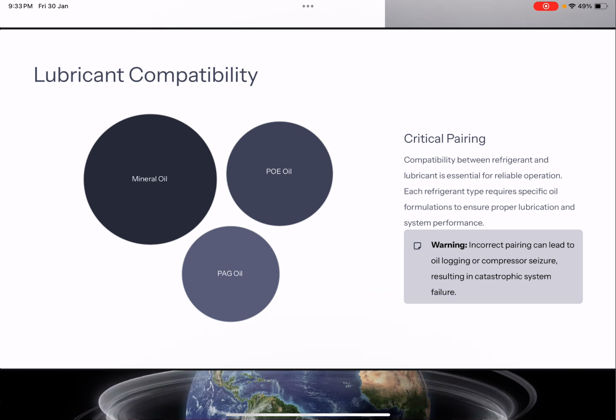As I said earlier, compatibility with the lubricant, essentially compatibility with mineral oil or POE, is important because that is going to affect the life of the components in the long term. If there is an incorrect pairing, meaning a refrigerant going along with an incompatible lubricant, then that might lead to oil logging or compressor seizure, and that would result in catastrophic system failure. So, in order to ensure proper lubrication in the long run, the refrigerant has to be compatible with the lubricant. There has to be a critical pairing.